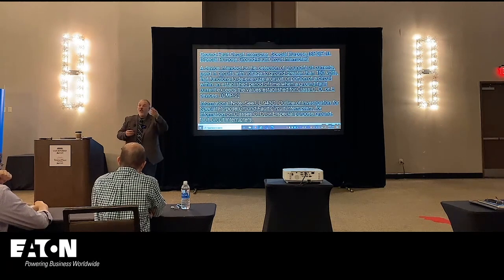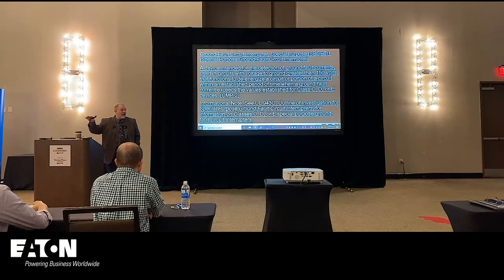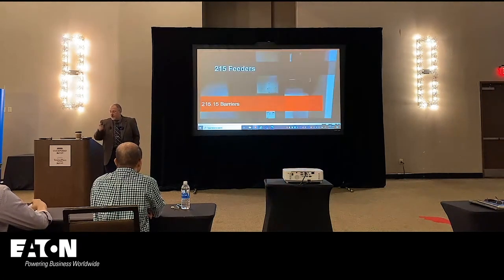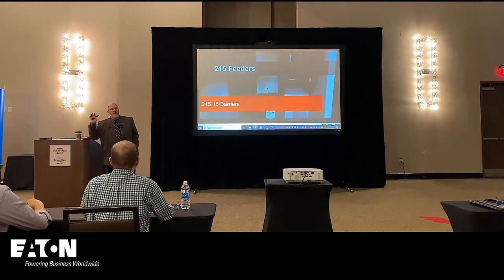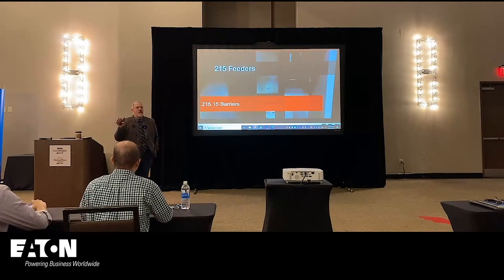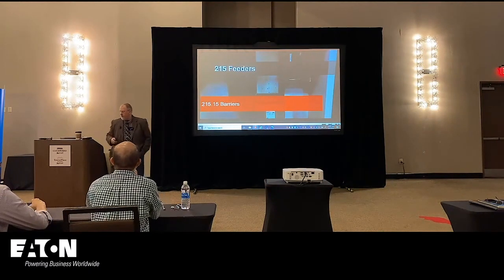The special purpose GFCI works off of that same principle. What they're doing is trying to control the voltage across the body, and they have assured grounding paths. There's software in there that makes sure the equipment grounding conductor is a certain size, so they know how much current will flow through the body if you come in contact. But these are applicable to greater than 120 volts, up in the 480 volt systems. So there are peppered requirements in swimming pools and, I believe, RV parks too.